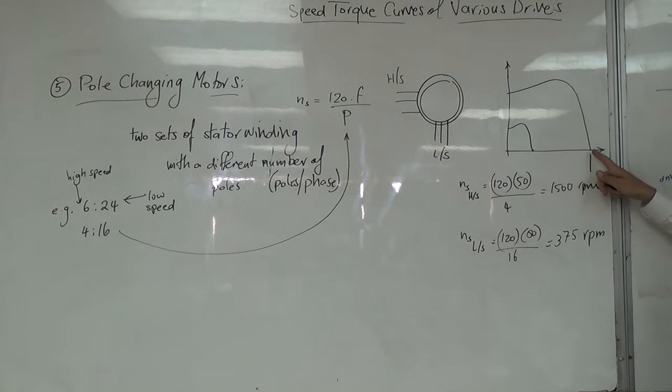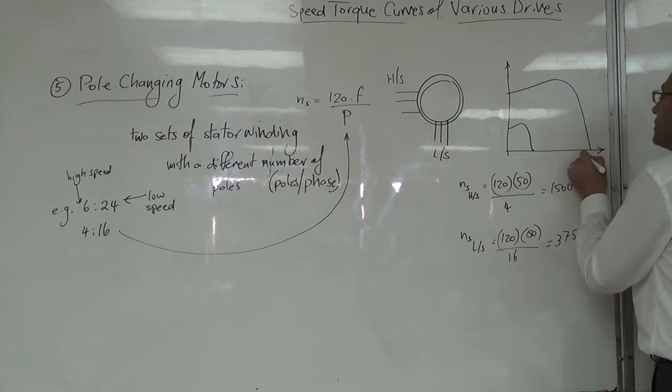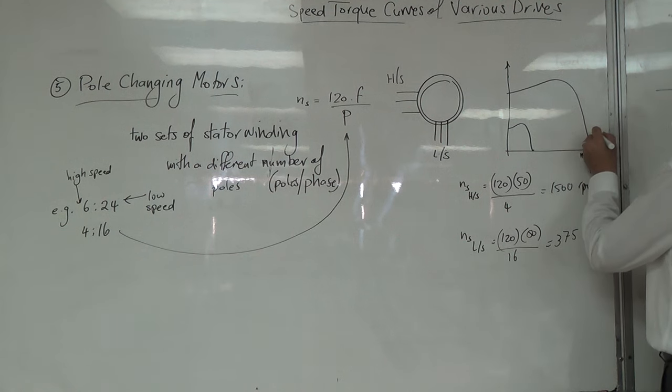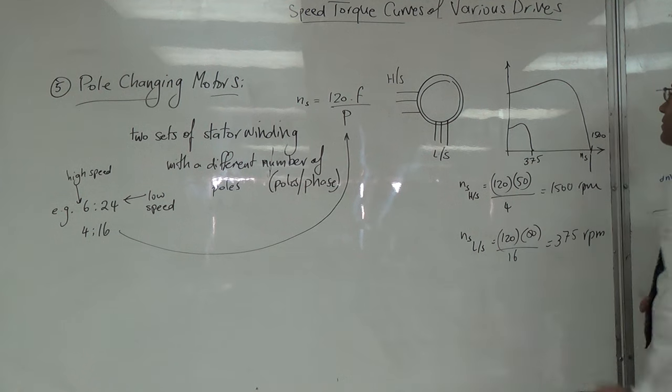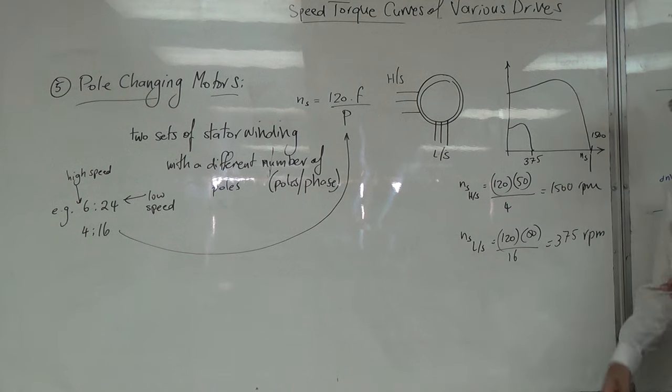الاختلاف بالـ poles سبب الاختلاف بالـ synchronous speed. فعندي هون ns sync هذه 1500 RPM، وهون ns sync 375 RPM. فنزلنا من هاي النقطة لهاي النقطة، ربع القيمة الأصلية.